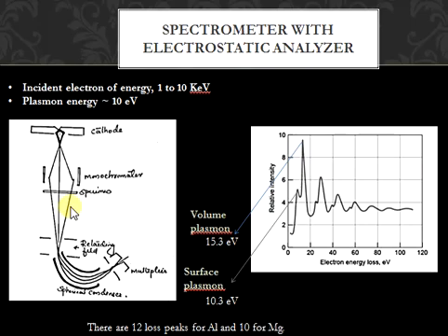This then passes to a spherical condenser, which contains different lenses, so that the beam is guided into a multiplier unit which counts the electrons. This is attached to a magnetic field based spectrometer, which can measure the electron energy loss that happens when the electrons are scattered through the metallic specimen.